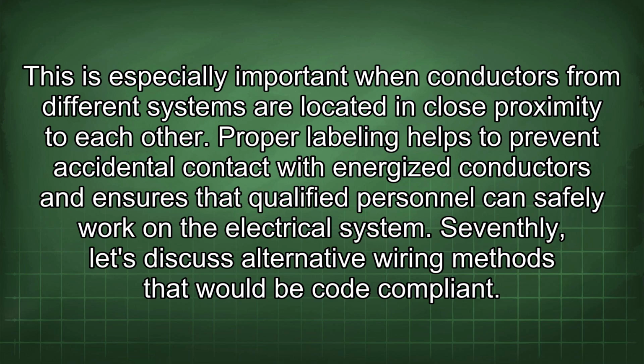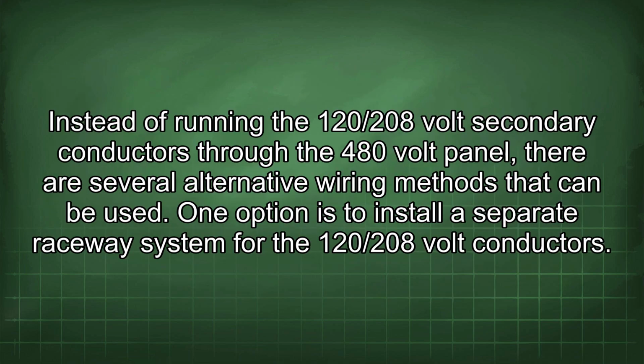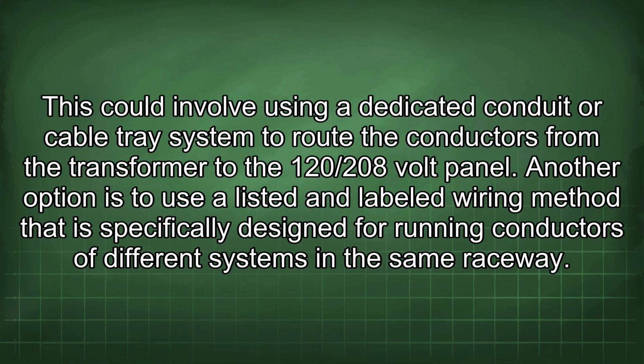Seventhly, let's discuss alternative wiring methods that would be code compliant. Instead of running the 120/208-volt secondary conductors through the 480-volt panel, there are several alternative wiring methods that can be used. One option is to install a separate raceway system for the 120/208-volt conductors. This could involve using a dedicated conduit or cable tray system to route the conductors from the transformer to the 120/208-volt panel.